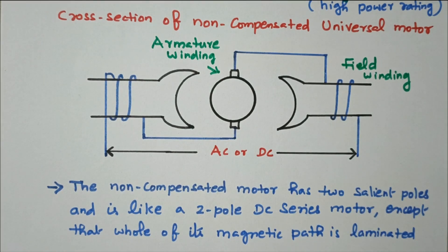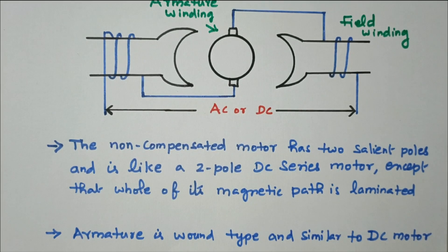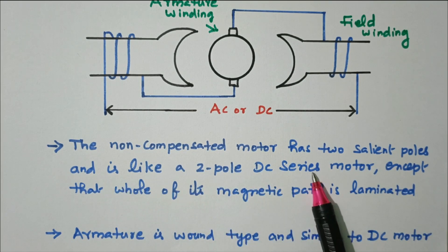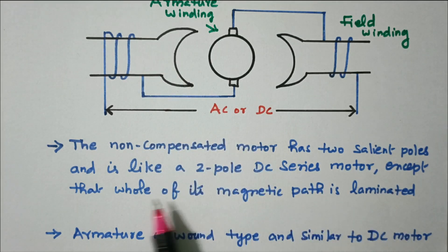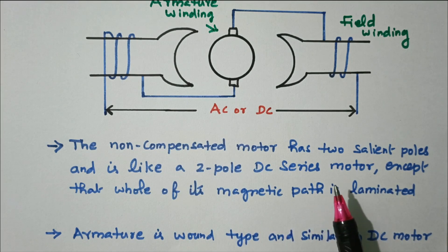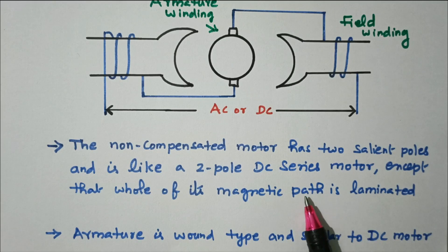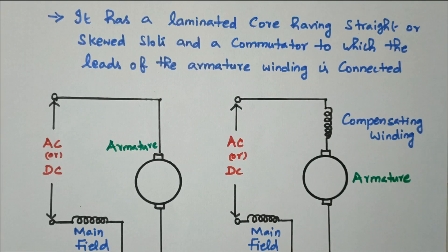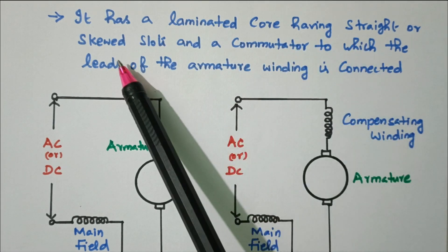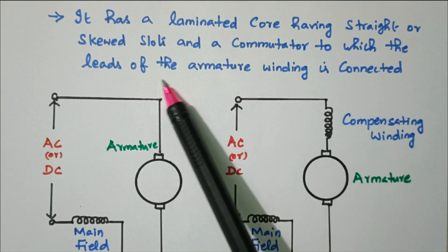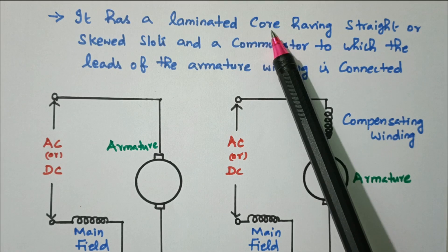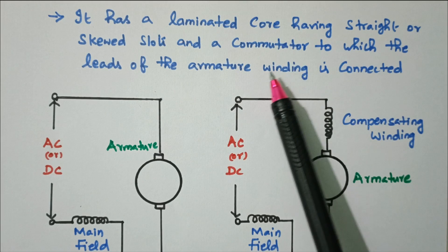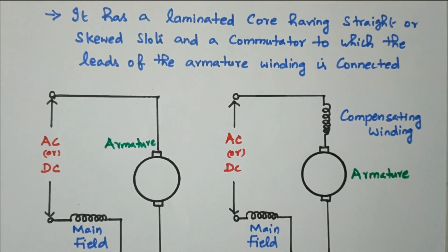The non-compensated motor has two salient poles — salient means projected — and it is like a two-pole DC motor, except that the whole of its magnetic path is laminated. The armature is wound type, similar to a DC motor armature. It has a laminated core having straight or skewed slots, and a commutator to which the leads of the armature winding are connected.